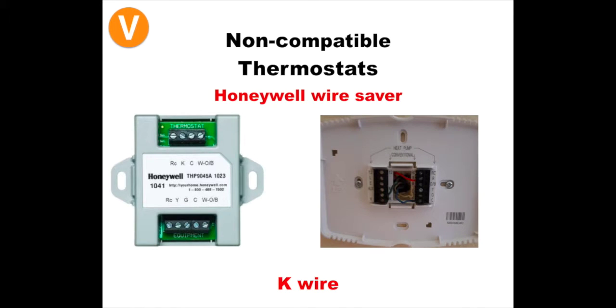All right, I've been getting calls every year on this type of thermostat. This is a Honeywell wire saver thermostat. Sometimes you'll see these are actually installed by power companies in certain states. The identifying factor on these thermostats is that they will have a K wire. In a lot of cases, they'll have an R wire, a C wire, maybe a W or a Y, and then they'll have the K. What happens with these thermostats is they can actually make a 4-wire system work as a 5-wire or a 6-wire. However many wires you need, it can actually convert a 4-wire into one of those types of systems.